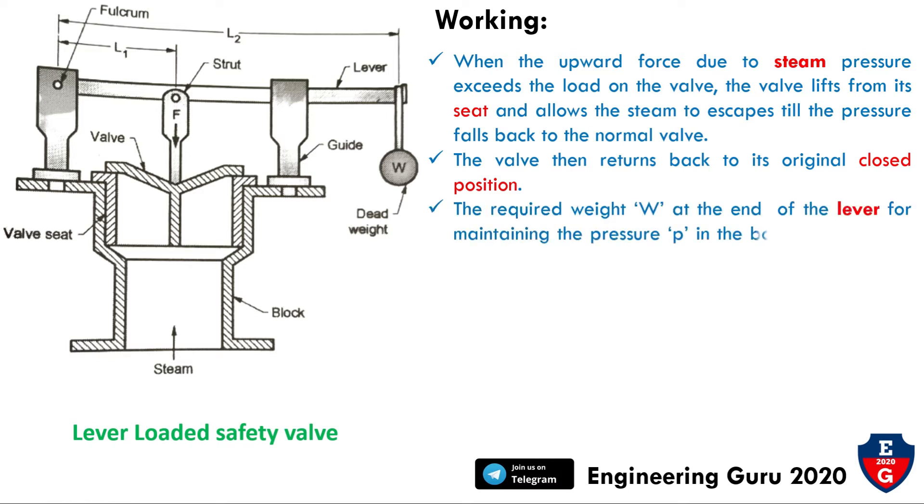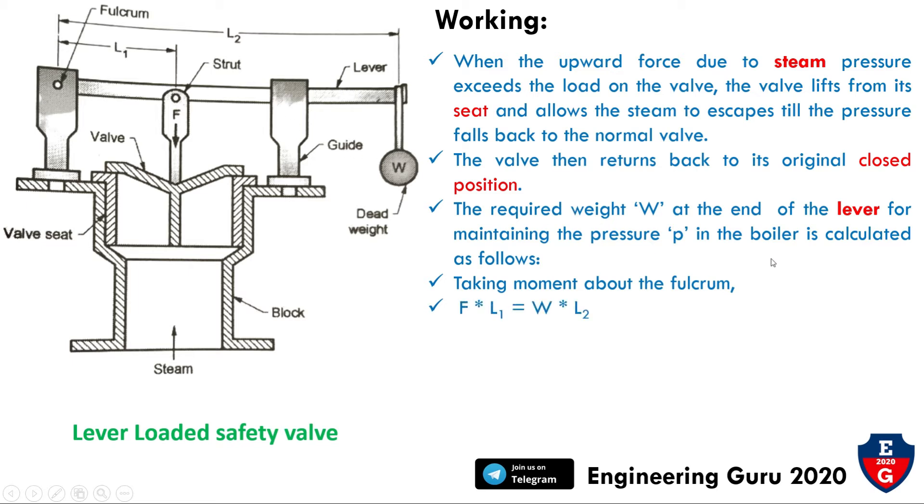The required weight W at the end of the lever for maintaining pressure P in the boiler is calculated by taking moments about the fulcrum. Moment equals force times distance, and at the fulcrum the net moment equals zero. So: F × L1 = W × L2, where F is the downward force on the valve through the strut, W is the weight at the end of the lever, and L1 and L2 are distances from the fulcrum to the valve center and center of weight respectively.